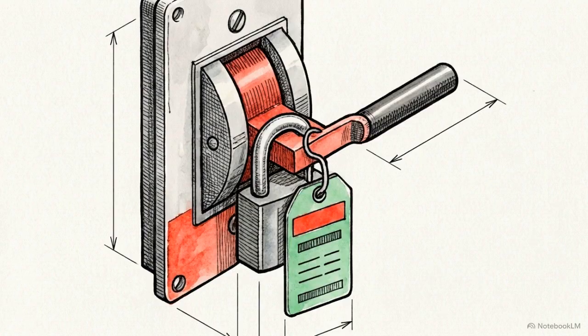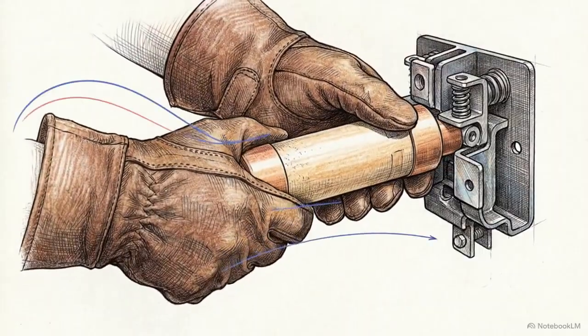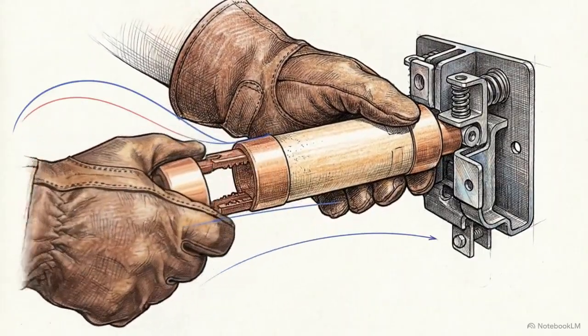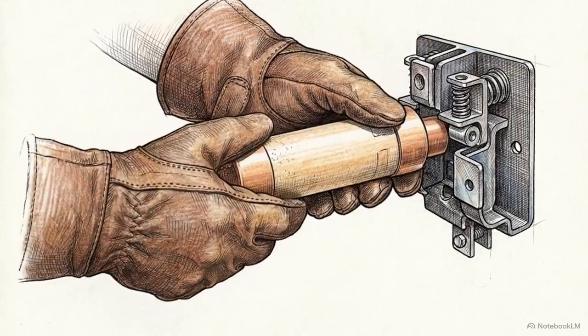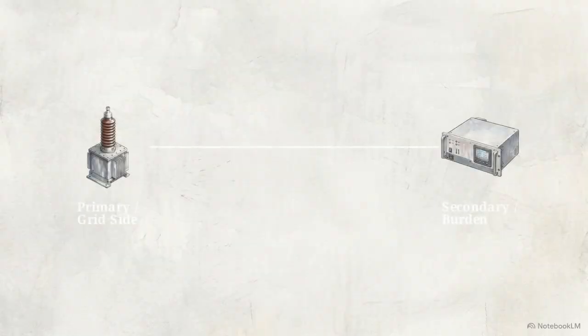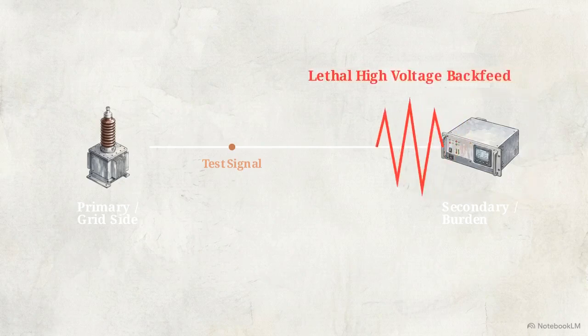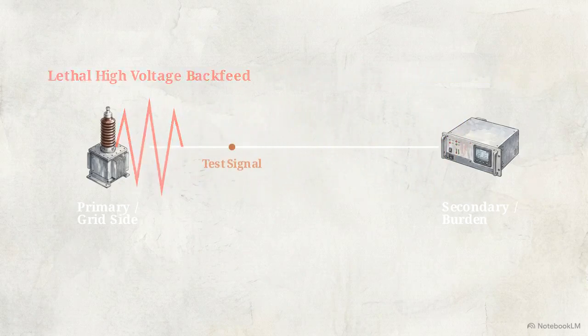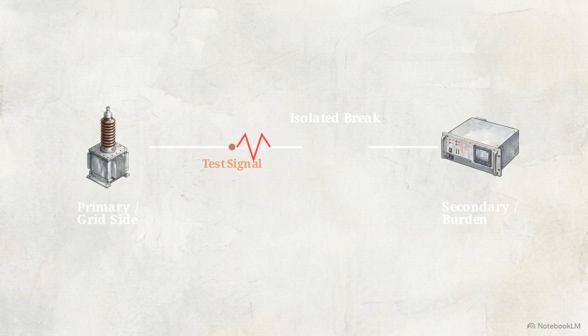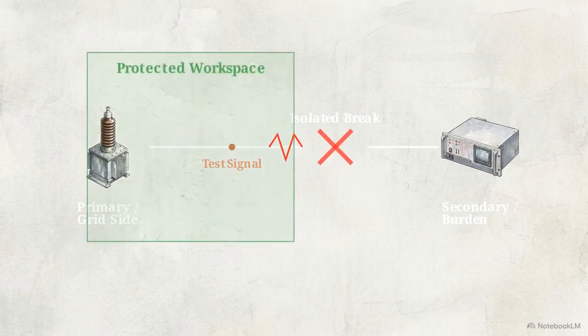Before any diagnostic probes are attached, the absolute baseline condition must be established. The VT must be explicitly de-energized and proven completely dead. The unit is then physically isolated from all secondary circuits. Every connected burden, link, and fuse is removed. This isolation prevents secondary backfeed. If test signals travel downstream into connected metering equipment or protection relays, those devices could inadvertently step the voltage back up, electrifying the immediate workspace.